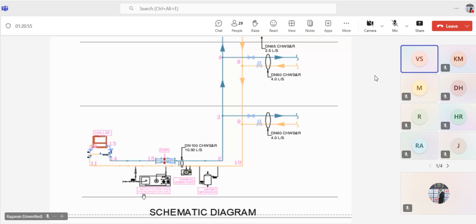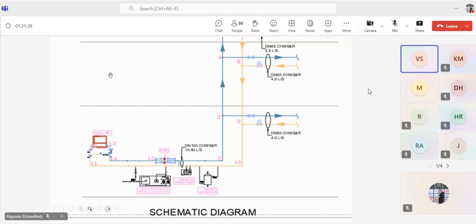But if you have a small building, whether high rise or low rise, it doesn't matter, and you don't have that much budget plus space, you usually need to go directly for an air cooled chiller. So for the air cooled chiller the delta T is different, and for the water cooled chiller the delta T is different. For example, with a water cooled chiller you will get 1.5 GPM per ton, but for an air cooled chiller it is 2.6 GPM per ton. It's an approximate value; it will go a little up and down, but this is the default value.